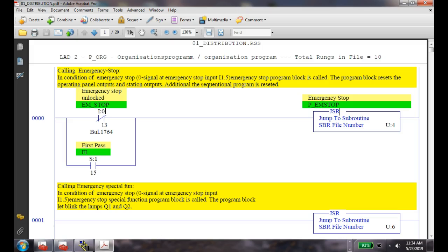They separate their bits. They don't use a slash, they use a period. So in Allen Bradley, if we use a period, we identify it as a word. In Siemens, if we use a period, we identify it as a bit. The way we identify words is with the type of port. So if I put I, that's what they call a boolean or 1 bit. If I put IB, it's a byte.